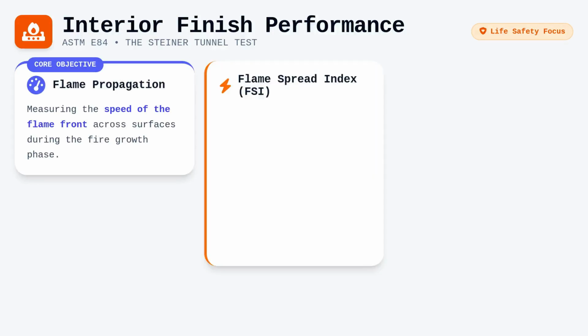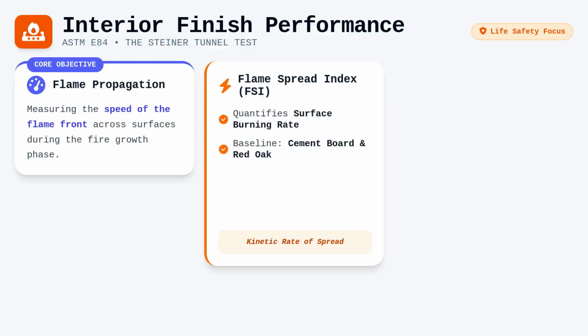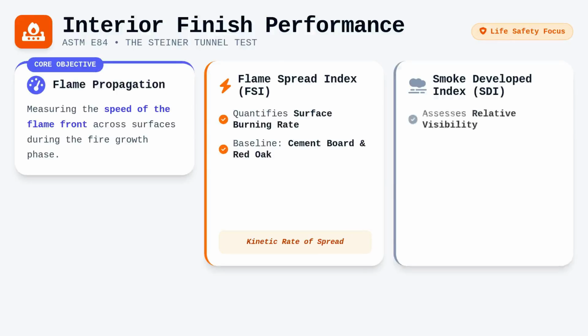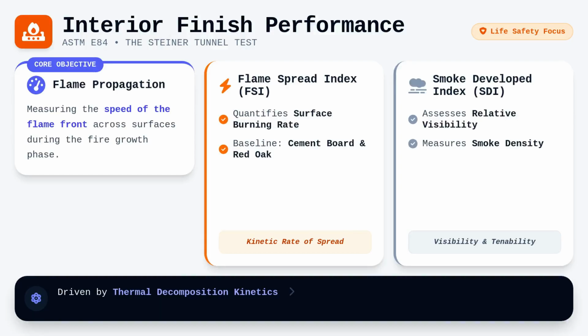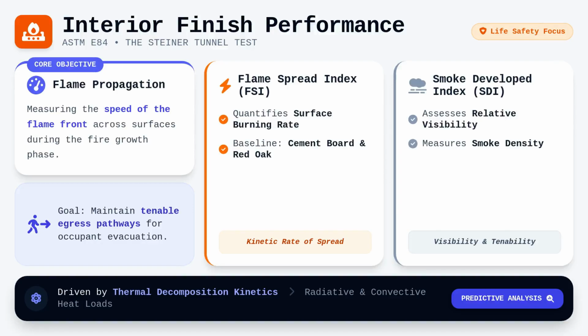The flame spread index, or FSI, provides a numerical value comparing the material's surface burning rate to that of inorganic reinforced cement board and select grade red oak flooring. Simultaneously, the Smoke Developed Index, or SDI, assesses the relative visibility through the smoke produced during the trial. These values are not arbitrary. They reflect the thermal decomposition kinetics of the material under specific radiative and convective heat loads. By understanding the physics behind these indices, you gain the ability to predict how architectural claddings will behave during the growth phase of a fire. This information is vital for ensuring that egress pathways remain tenable for occupants during a fire event.